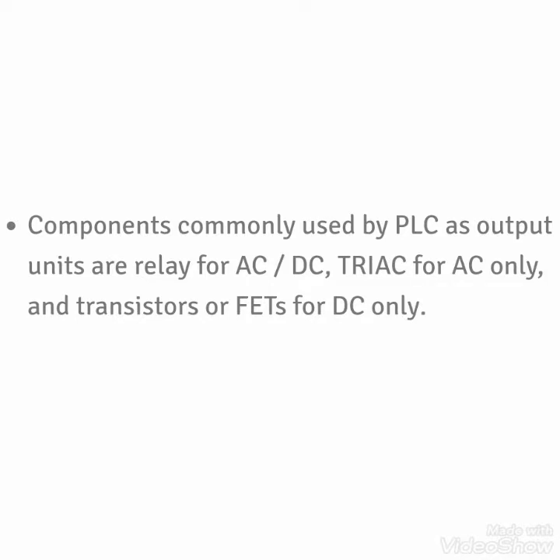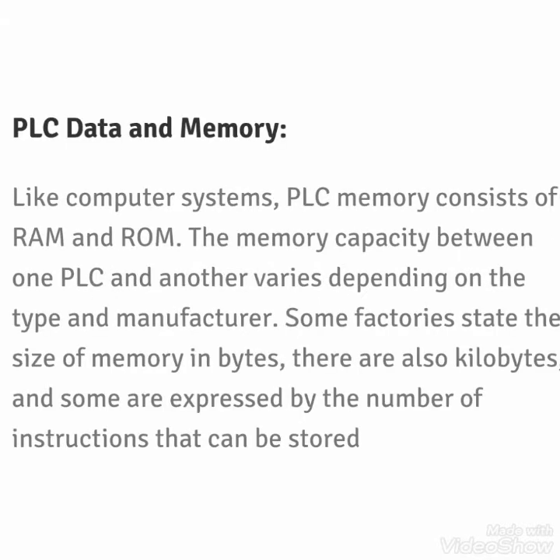Components commonly used by PLC as output units are relays for AC/DC, triacs for AC only, and transistors or FETs for DC only.